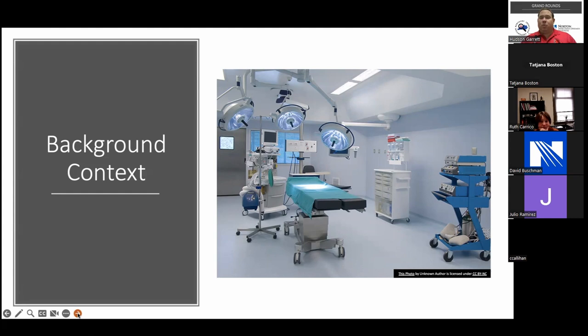I'll give an example Ruth and I are both very familiar with: ultrasound probes used for vascular access device placement. If you're scanning intact skin, that's not a problem. But the second you make a break or a nick, or use a scalpel in that skin and then scan across it, that skin is no longer sterile or intact. The device itself can actually contaminate that, and it changes the level of disinfection and reprocessing we should really try to accomplish.